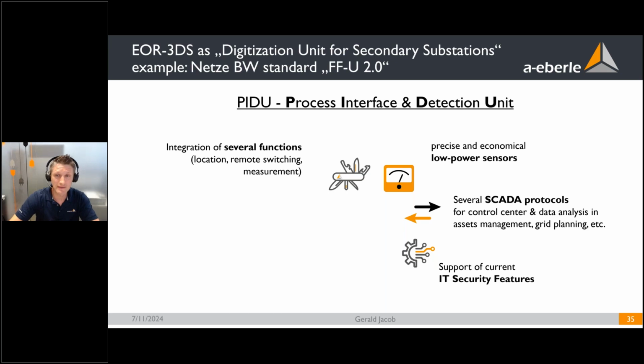The complete station is completely Ethernet based, so they really have no analog protocol, no Modbus RTU. There's a big difference to the E.ON concept here in Germany. That is digital until the RTU, but under the RTU, in the direction of the earth fault indicators, everything is in a serial manner. Here, this concept is totally different. Every device is connected via Ethernet and has to support the relevant IT security features.